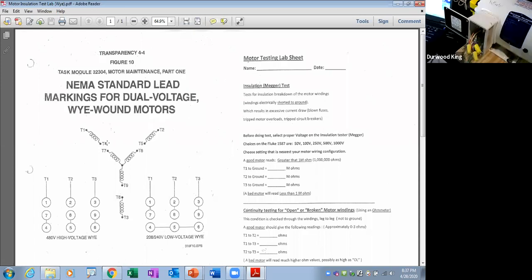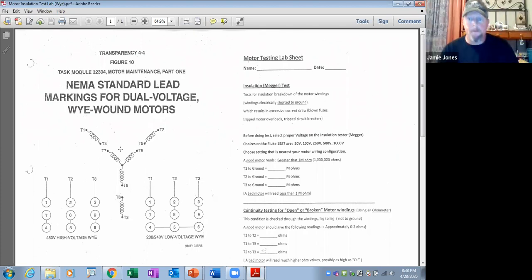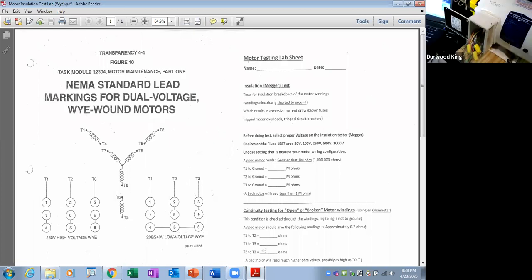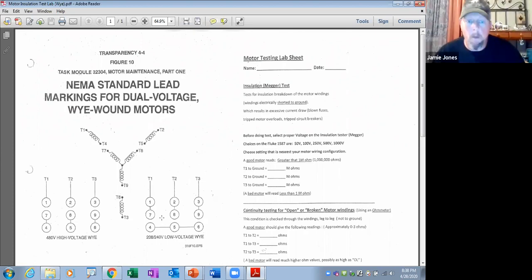Now look at here. When you tie 4 and 5 and 6 together, what you've done is you formed another Y here. You got a Y in here, but you've got another Y constructed of this winding, and that one. And they form another center connection for a Y with 4, 5, and 6. You see that? Everybody see that? Yes. Oh, you have a double Y. If it's parallel, if it's low voltage Y, it's called a double Y. You have a Y here, and you got a Y out here. There's 2 Ys, 2 Y windings, and they're in parallel on low voltage. That makes sense? Yeah. Okay, so just keep that in mind.